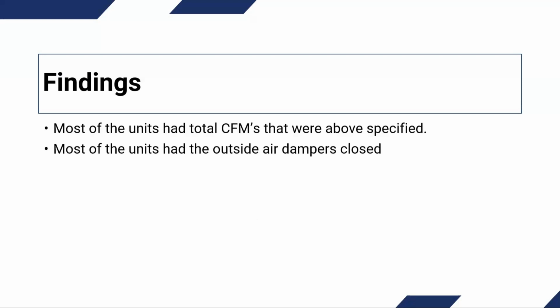Most of the units, if not all the units, had the outside air dampers closed. Again, this was most likely done by the staff because they had a humid building. They need to resolve the humidity issues. So the first thing they do is shut down the outside air, which of course did not solve their humidity problem. That's one of the things that we try to stress to clients: I haven't seen a project yet where dropping the temperature down to 66 or 68 or shutting the outside air has ever solved their problem. So we always recommend that they don't bother trying to do those two things because it's not going to fix the problems.